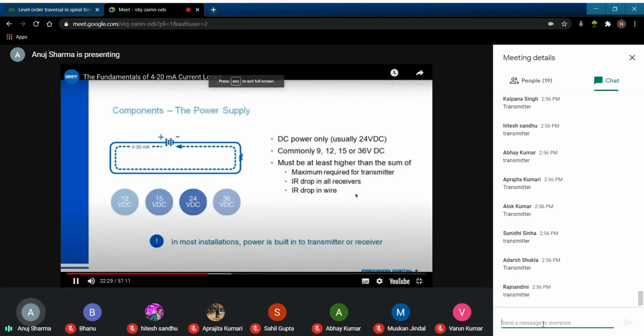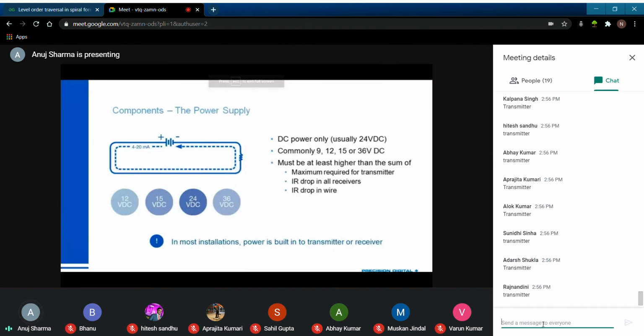And trying to run it with a 9-volt power supply, because regardless of how small the voltage drops may be across other pieces of equipment, that 18 volts in your transmitter is going to sink that 9-volt supply, and suddenly your system is not going to work. So it's critical, especially with 2-wire devices, that you know what your voltage drops are going to be, so you know if your power supply can support that loop.